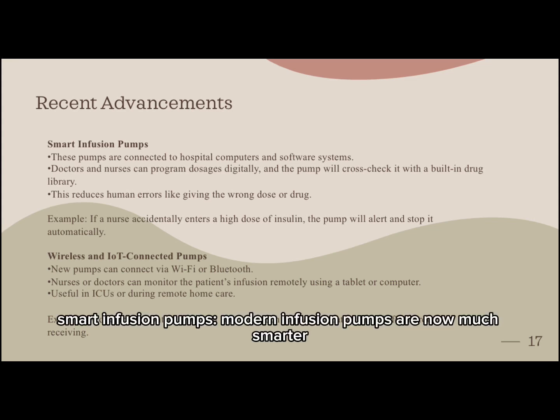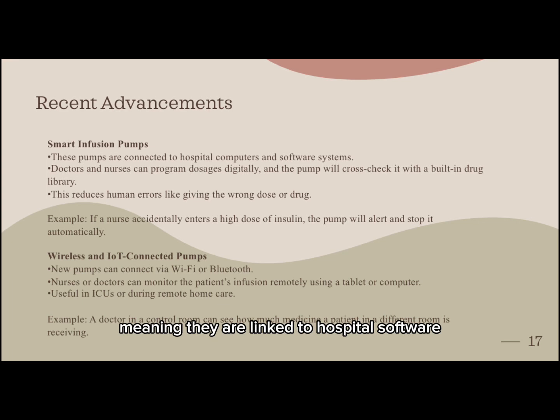Smart infusion pumps. Modern infusion pumps are now much smarter, meaning they are linked to hospital software, allowing medication doses to be set electronically. The pump checks the dose against a drug database before starting the infusion, acting like a second pair of eyes to catch human mistakes. For example, if a wrong insulin dose is entered, the pump immediately recognizes it and alerts the staff.